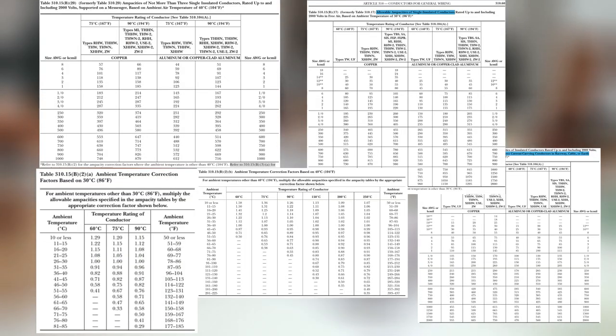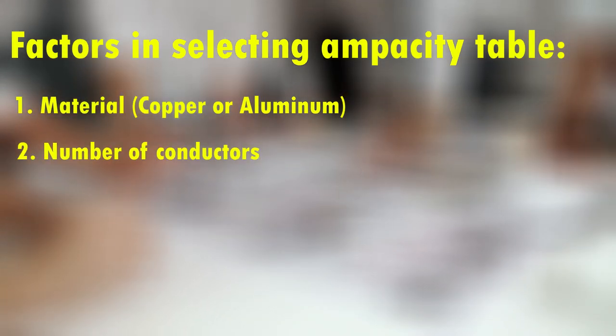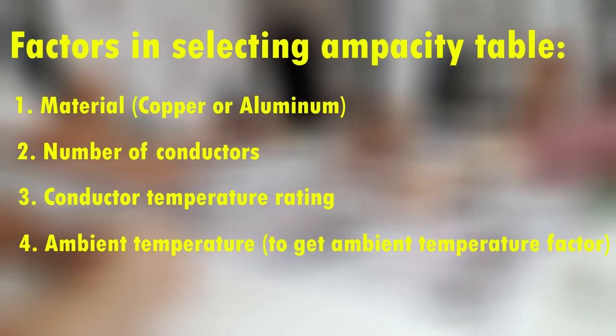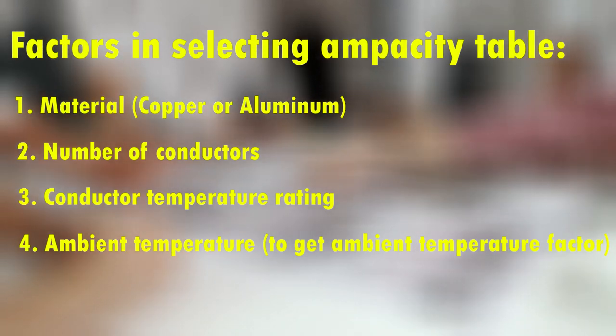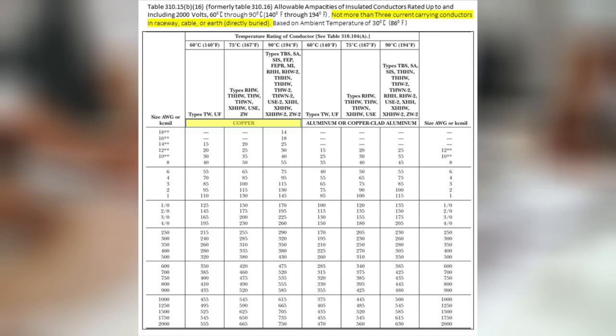We have a table from the National Electric Code (NEC) with different tables provided for ampacity rating. We need to consider several factors: copper or aluminum conductor material, the number of conductors, conductor temperature rating, and ambient temperature. By knowing the actual ambient temperature, we can select the appropriate ambient temperature correction factor table. For this example, we will use the table with the following conditions: copper wire, not more than 3 conductors, 60°C to 90°C temperature rating, and 30°C ambient temperature.